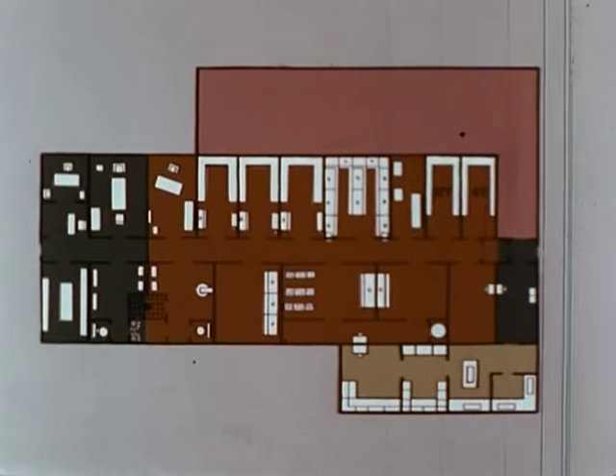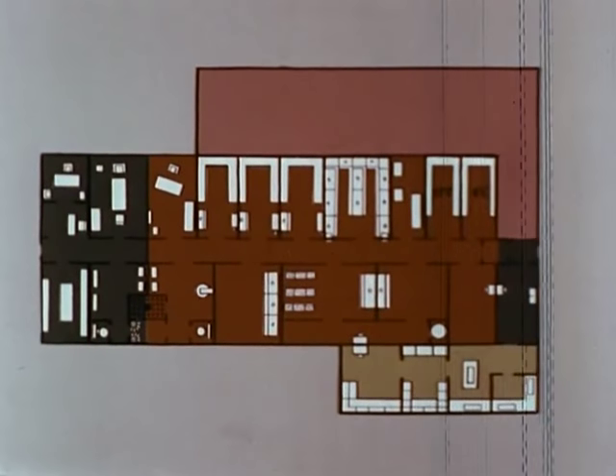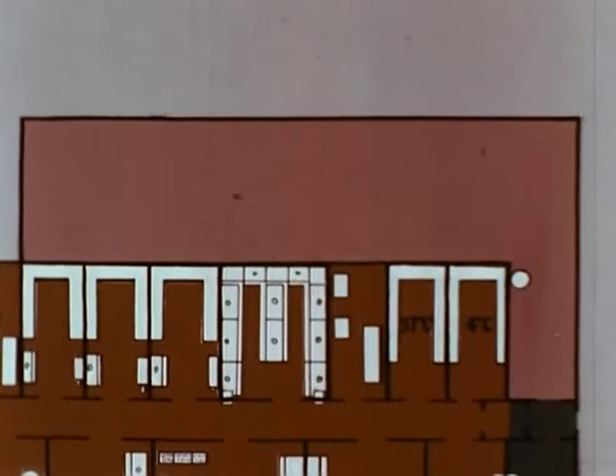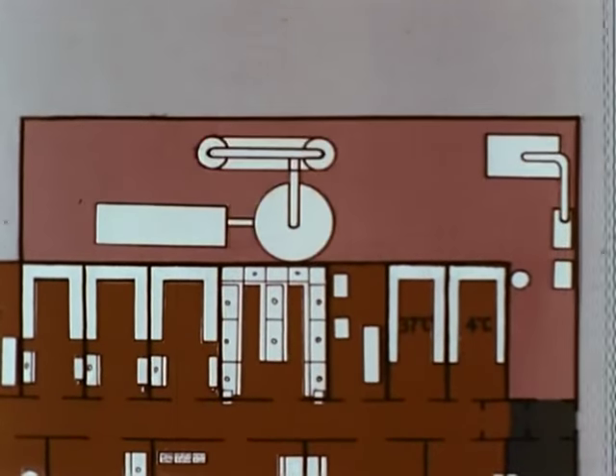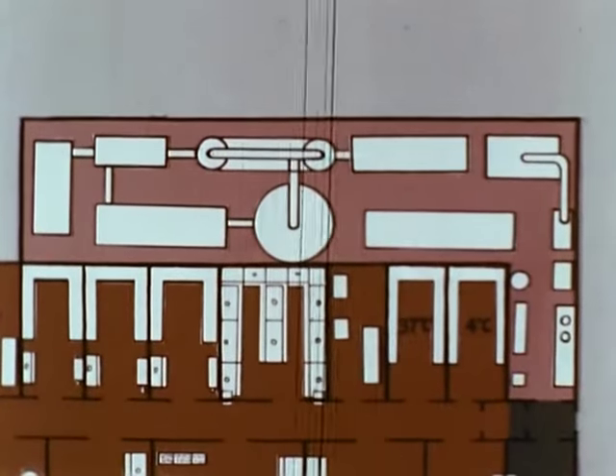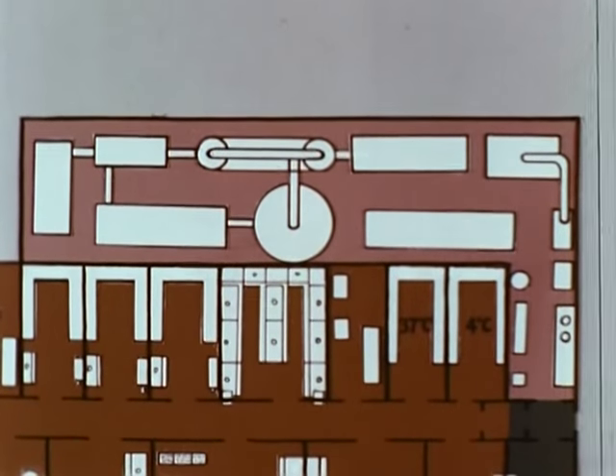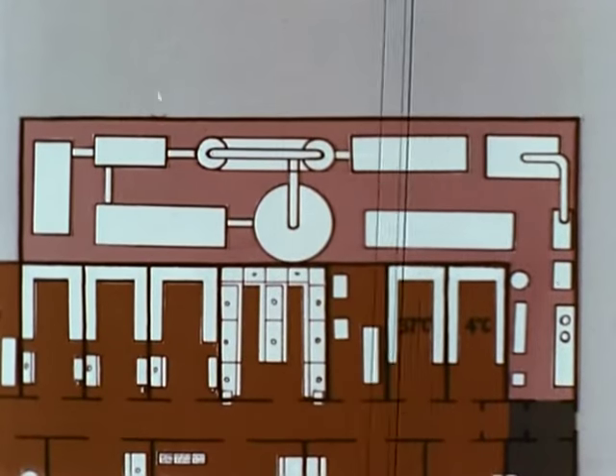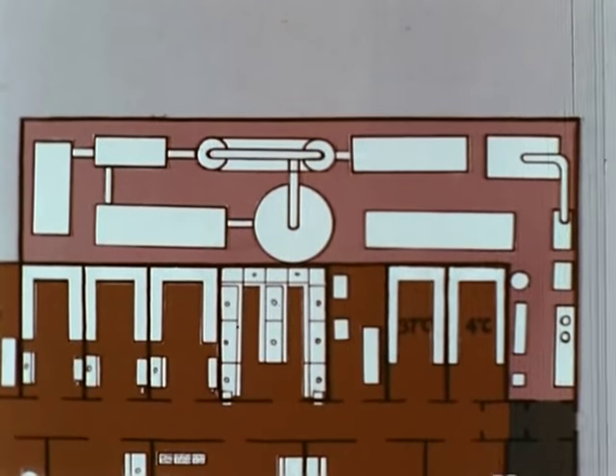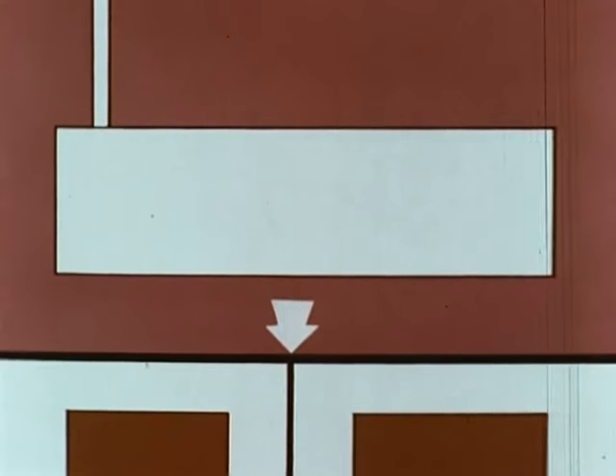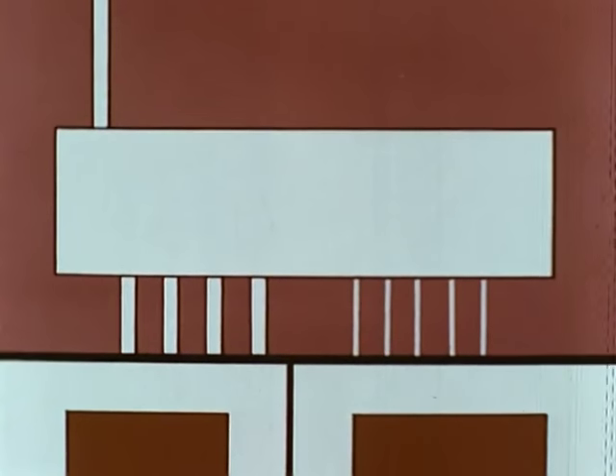The fifth functional zone in the lab facility provides engineering support. Included here are the necessary pipes, ducts, pumps, blowers, and filters, as well as the liquid waste treatment system and the bulk of the air handling system. Special engineering arrangements should maintain the integrity of the secondary barrier when penetration of the wall is made by pipes, wires, and ducts, regardless of whether the engineering zone is located on the same or a different level from the other functional zones.